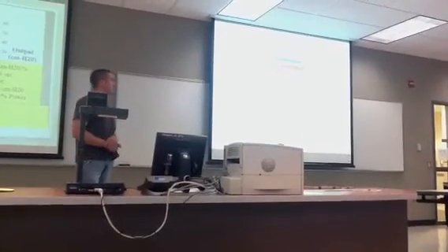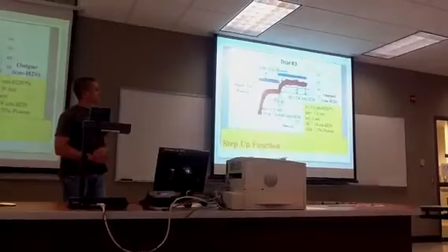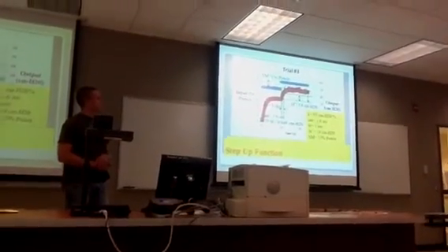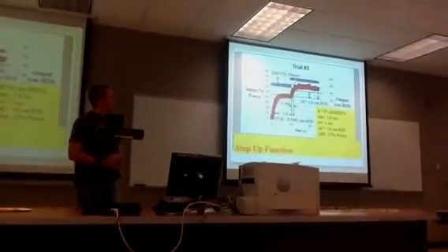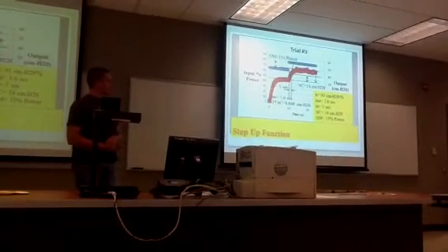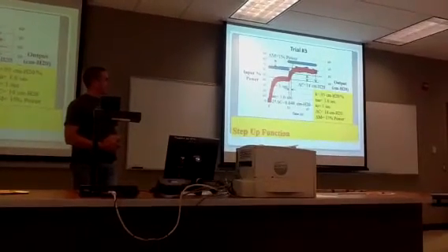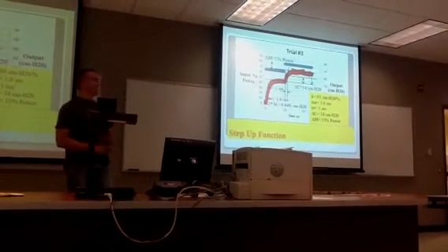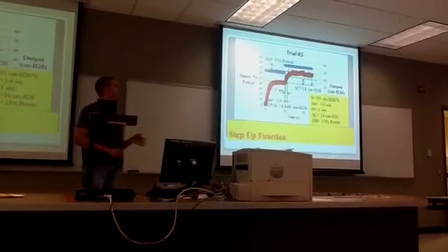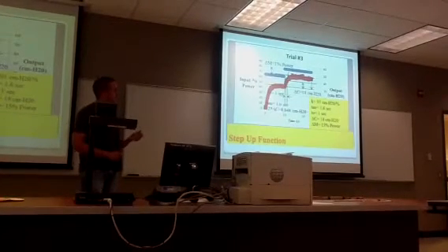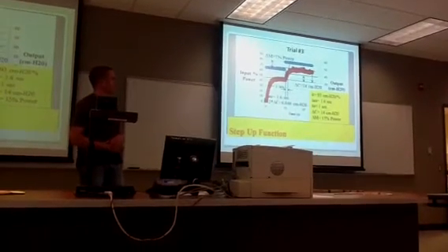This was an example of the step function. In the step function for this particular trial, the input was 65%, and then there was a step up of 15% power. From this data, we can calculate what the dead time, T0, was, and it was 0.1 seconds for most of the inputs. They responded very quickly, so it made it hard to measure.